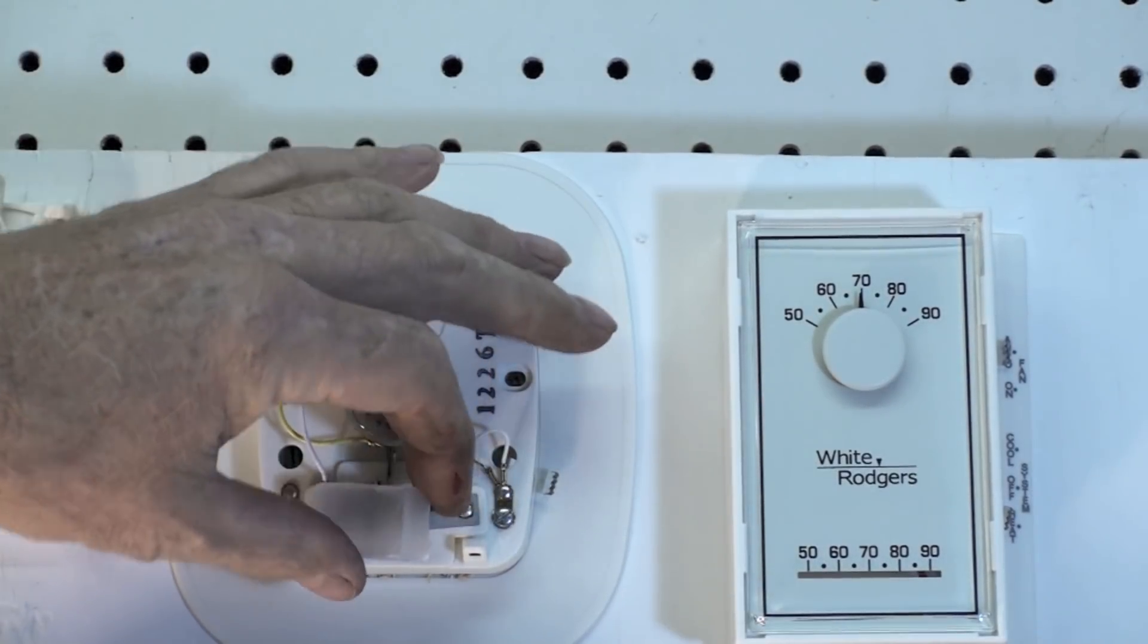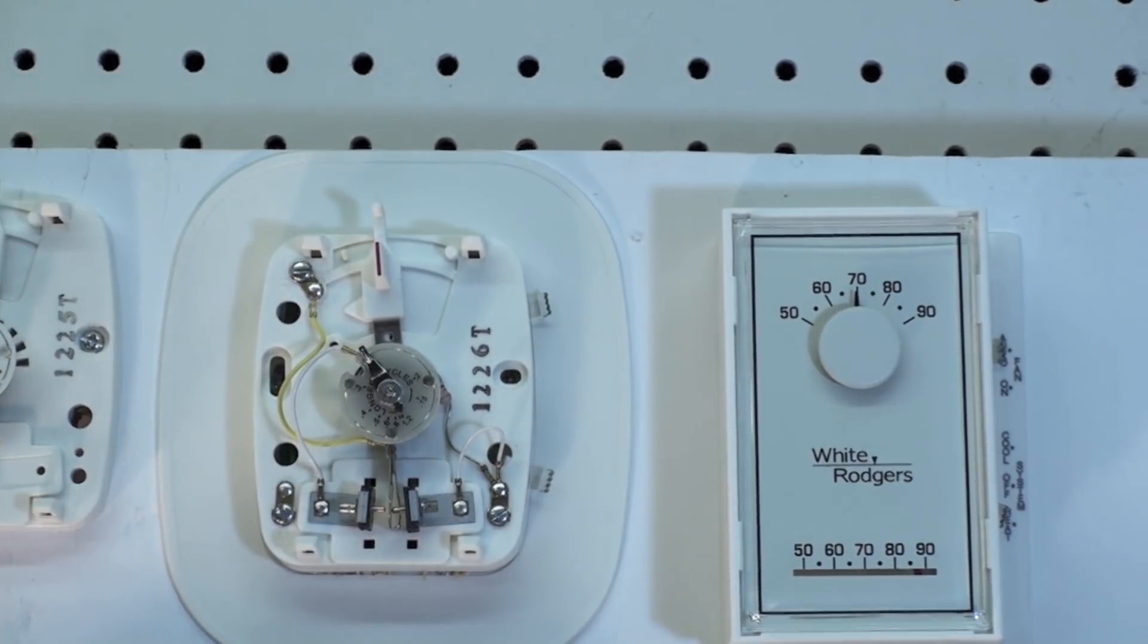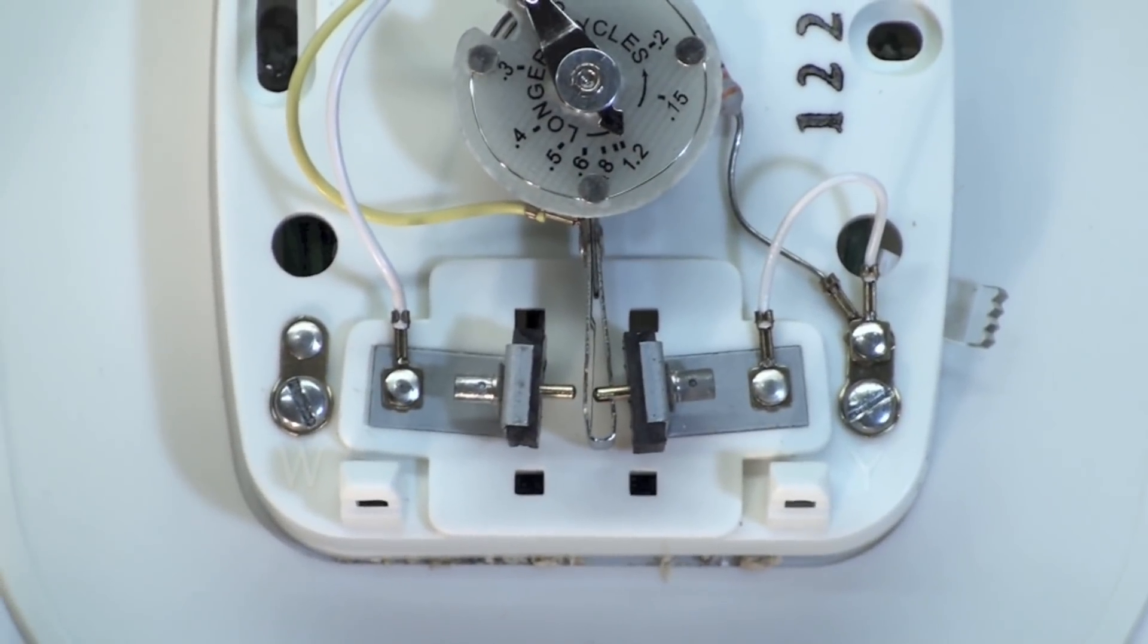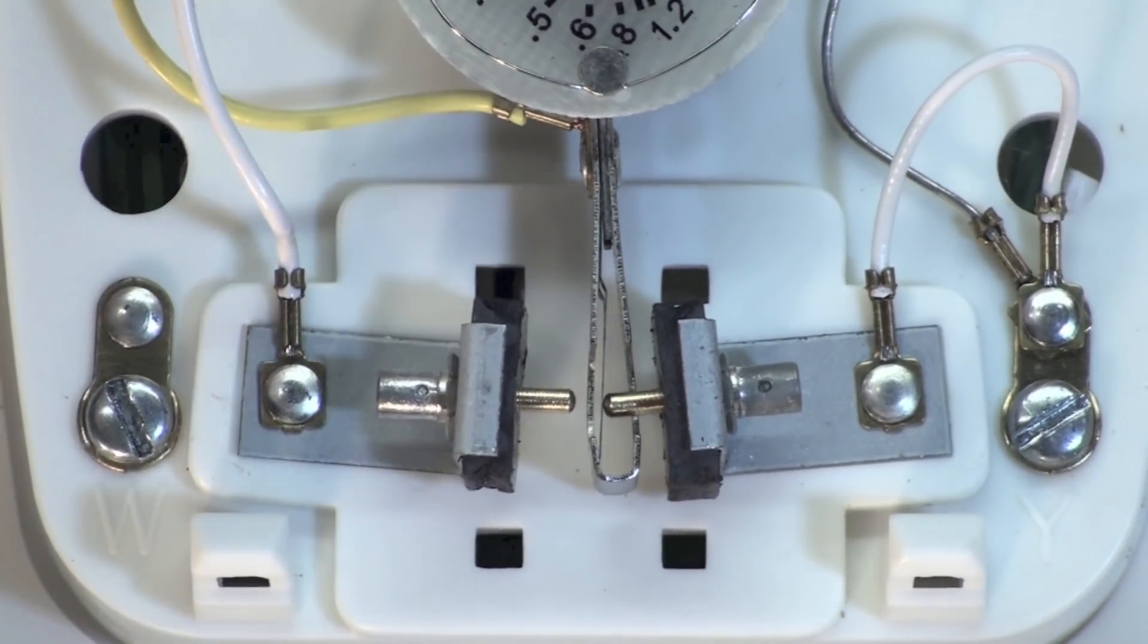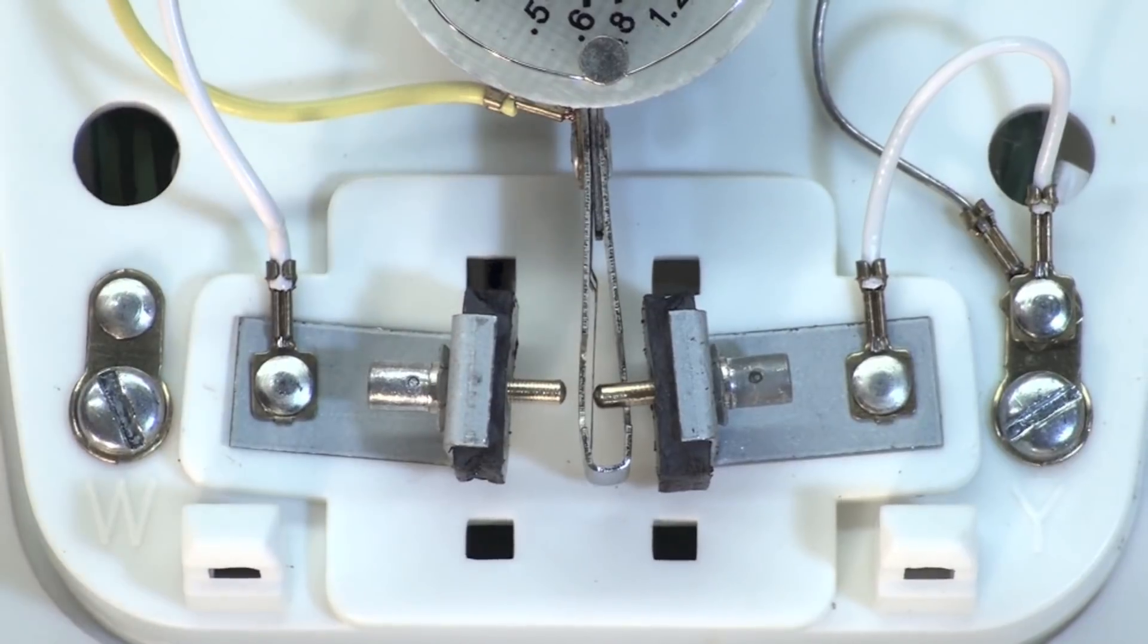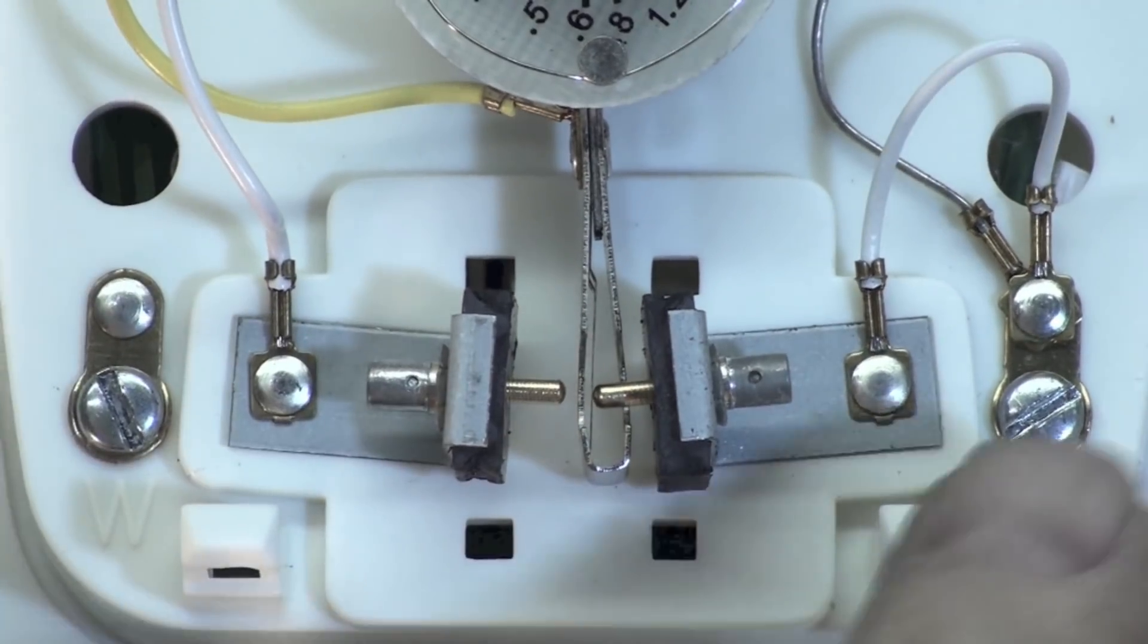This heating and cooling stat, the only difference between the first one I showed you and this one - by the way these things all have covers on them, don't lose the covers - this one's got two sets of contacts. You can see that better. As the lever moves back and forth it makes both, clicks over here, clicks over there. The other one only had one set of contacts but this has got a set of contacts here and a set of contacts there, so it could make for heating or cooling.